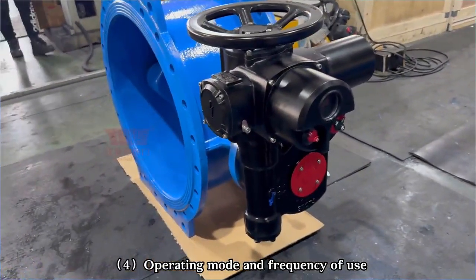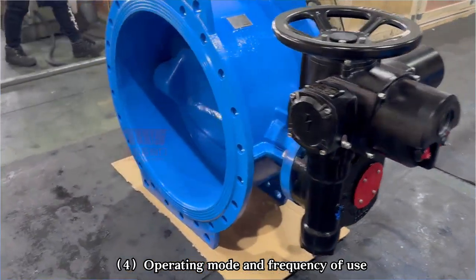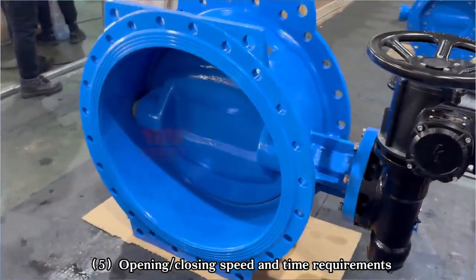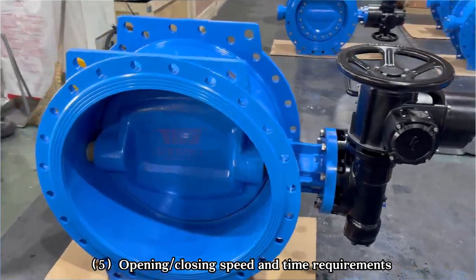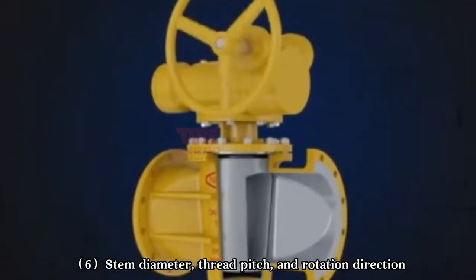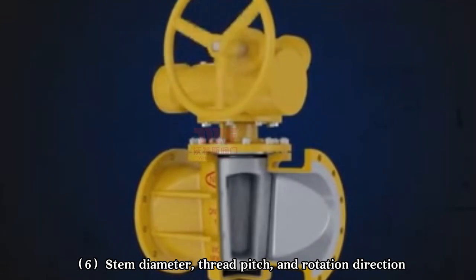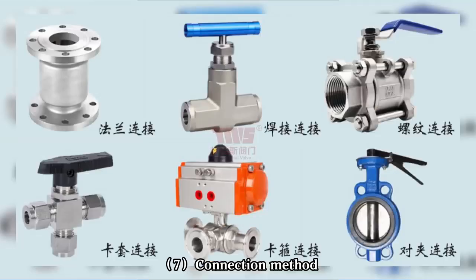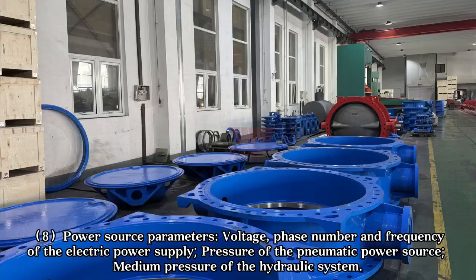4. Operating mode and frequency of use. 5. Opening and closing speed and time requirements. 6. Stem diameter, thread pitch, and rotation direction. 7. Connection method. 8. Power source parameters: voltage, phase number and frequency of the electric power supply, pressure of the pneumatic power source, medium pressure of the hydraulic system.